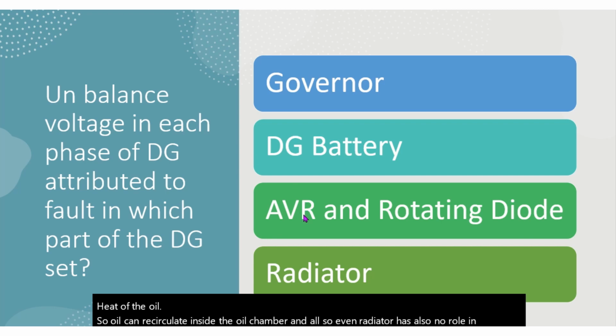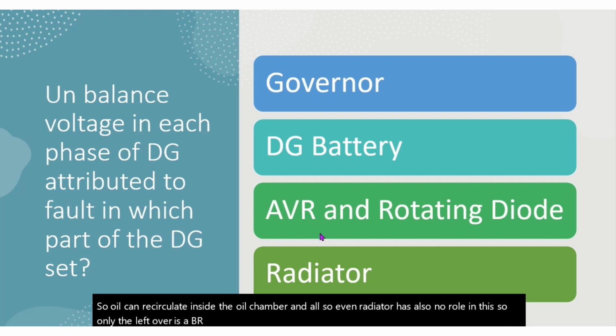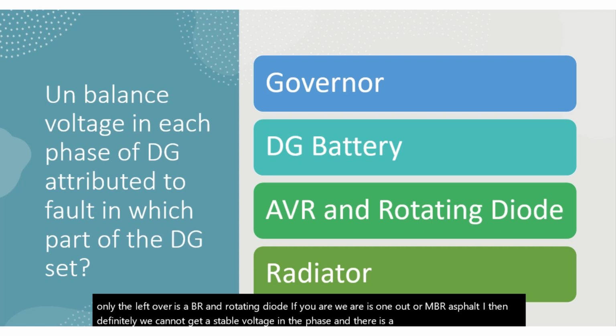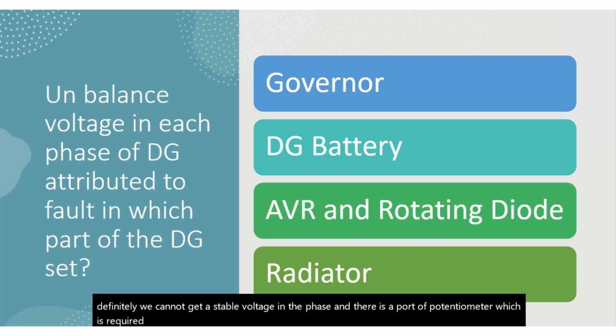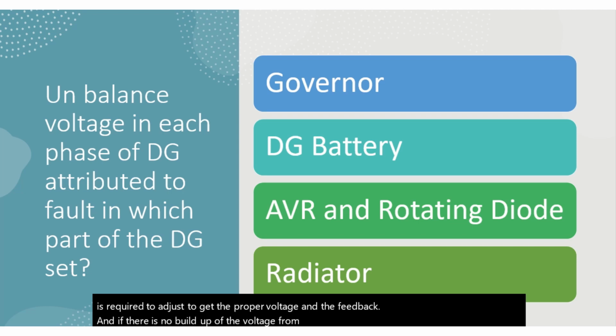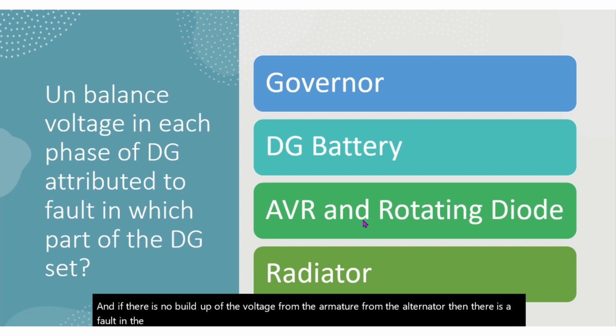So the only leftover is AVR and rotating diode. If your AVR is worn out or faulty, then definitely we cannot get a stable voltage in the phase, and there is a potentiometer which is required to adjust to get the proper voltage and feedback. And if there is no buildup of voltage from the armature or the alternator, then there is a fault in the rotating diode. So AVR and rotating diode is the correct answer in case of unbalanced voltage in the DG set.